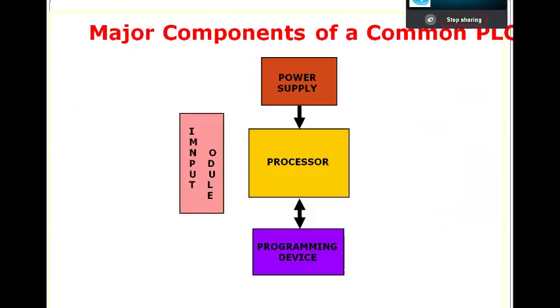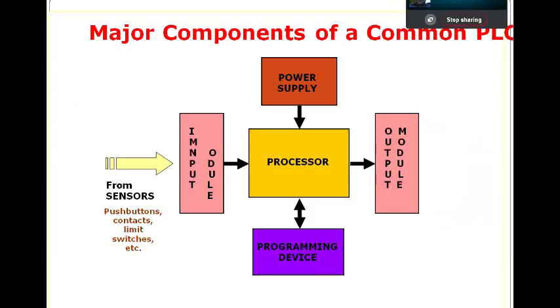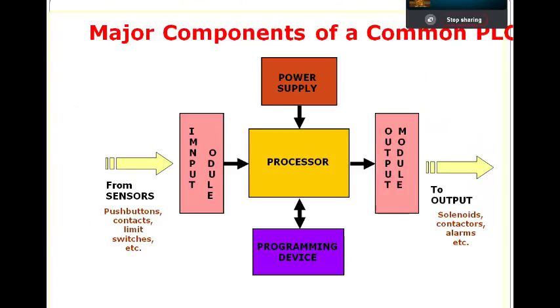The input module is the interface between your field elements — field sensors, field switches — and your PLC. It gets signals from sensors and sends them to the processor. The output module sends output to your final control element. When an analog value comes from a field sensor, the input module converts that analog value to digital using an analog-to-digital converter, because the processor only understands digital.